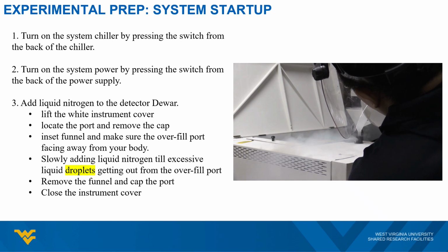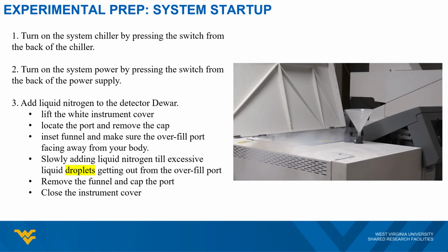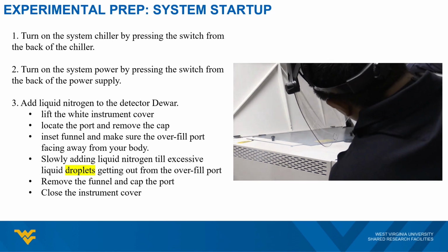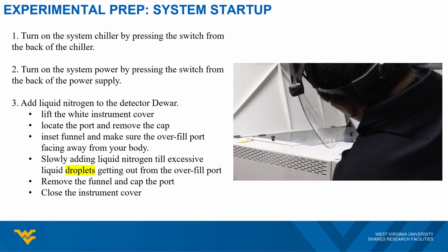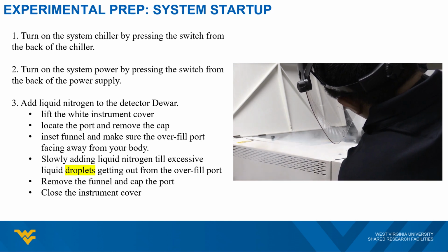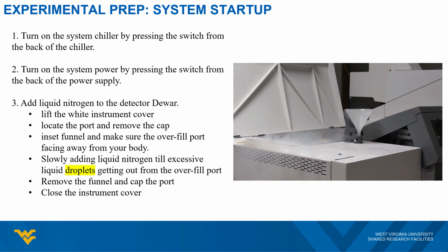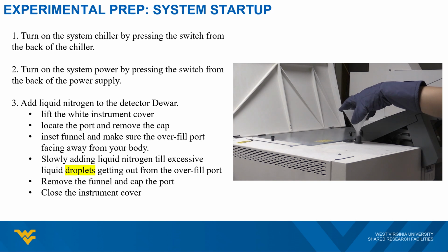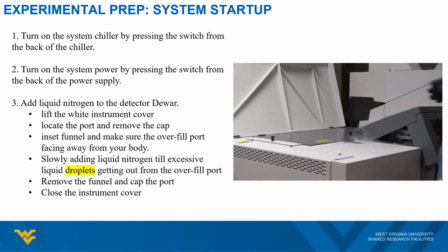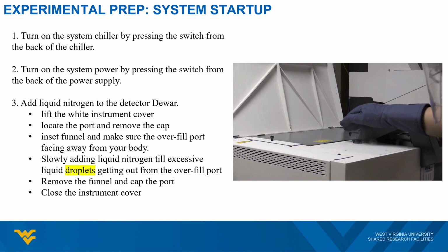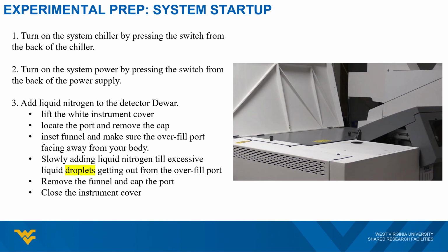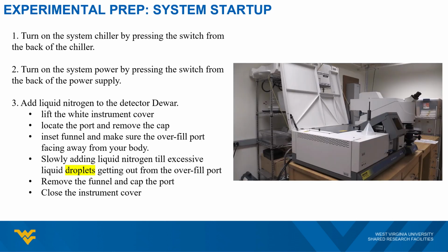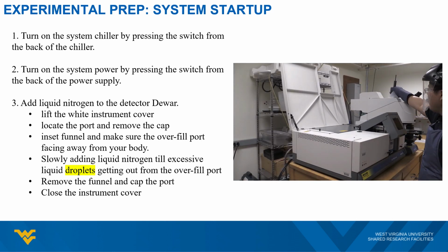Eventually, large droplets of liquid nitrogen will begin to exit from the port. This is the sign that the dewar is full and it's time to stop adding liquid nitrogen. Once that's done, remove the funnel and cap the port. Then close the instrument cover.